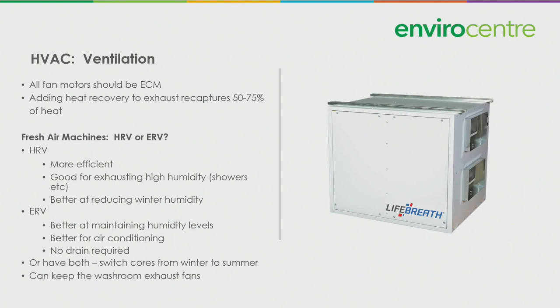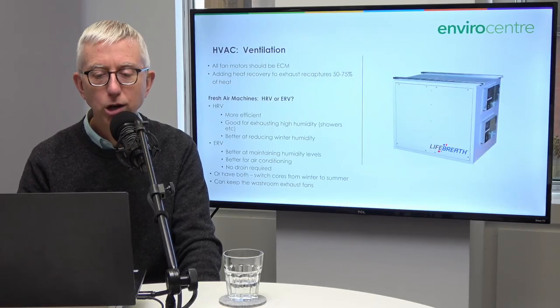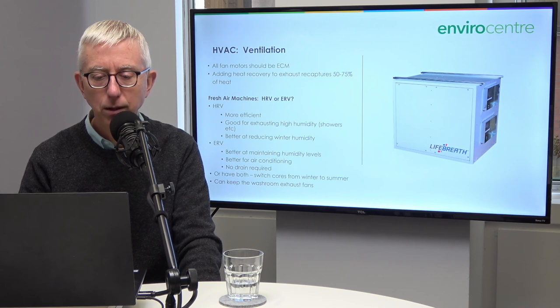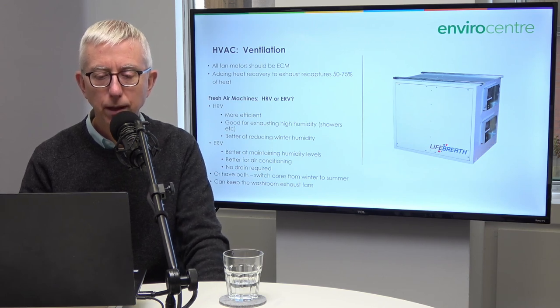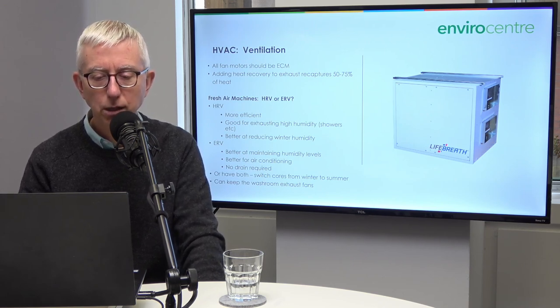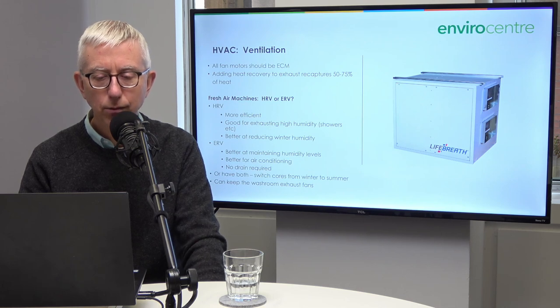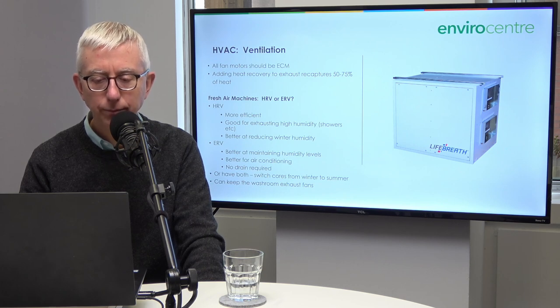You can also have both. You can buy an extra core for your HRV and you can switch it out from winter to summer so that you can have the best of both worlds. By the way, you can keep your washroom exhaust fans in these situations, or you can replace them depending on what you want to do with your system. It's more efficient, generally in a commercial situation, to replace the washroom exhaust fans with an HRV that's running continually, or an ERV.